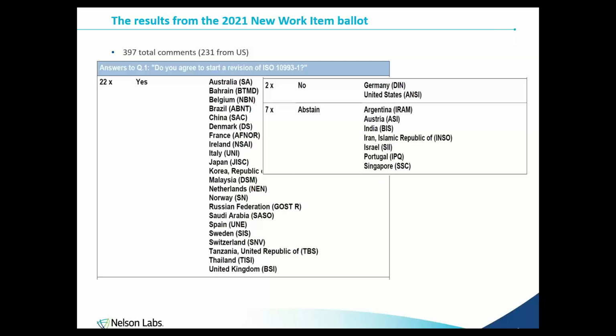So we're still a little uncertain exactly how the FDA is going to deal with this new standard. I am almost sure that it's going to be a partial recognition. The things we're talking about today might still be enforced. There are definitely some that are already being enforced, like end of life and particulate, and the cumulative use duration, and the genotoxicity, I guess. So pretty much everything we're talking about today, the FDA is going to enforce or recognize.